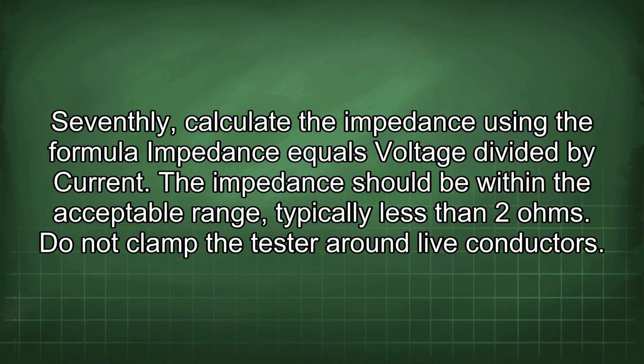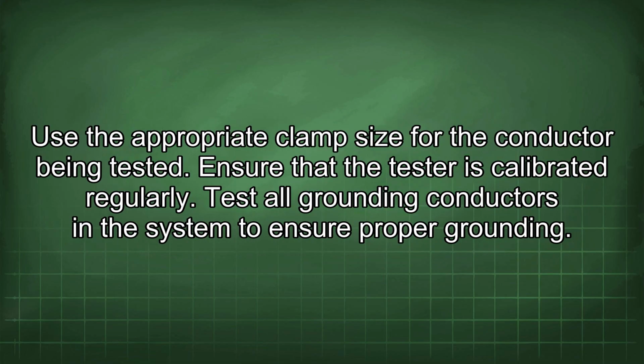The impedance should be within the acceptable range, typically less than 2 ohms. Do not clamp the tester around live conductors. Use the appropriate clamp size for the conductor being tested. Ensure that the tester is calibrated regularly. Test all grounding conductors in the system to ensure proper grounding.